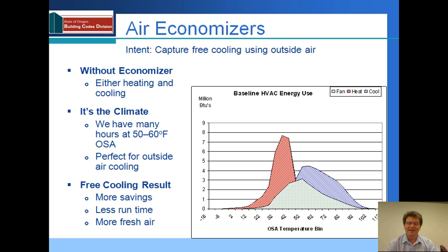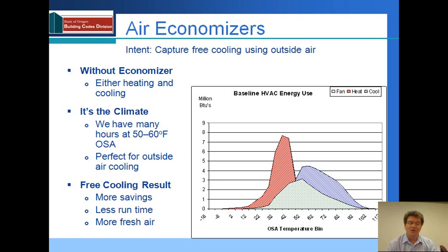We see our heating, ventilating, and air conditioning energy use graph. We've got outside air temperature along the bottom of the scale. We can see that when it's extremely hot or extremely cold, there is not a whole lot of energy use. We do have significant energy use in the middle of the spectrum because we have a lot more hours when the temperature is moderate. In fact, between 50 and 65 degrees or so, we can take advantage of some significant savings by using outside air for cooling.